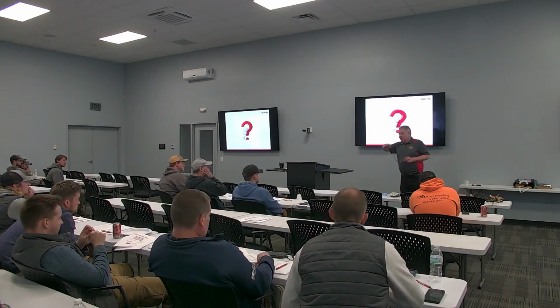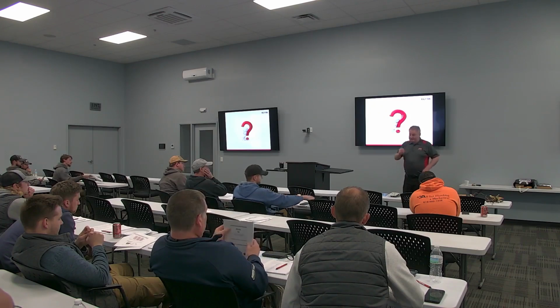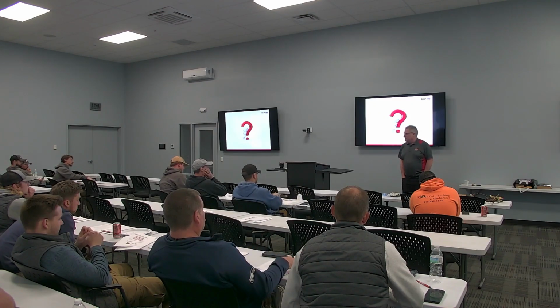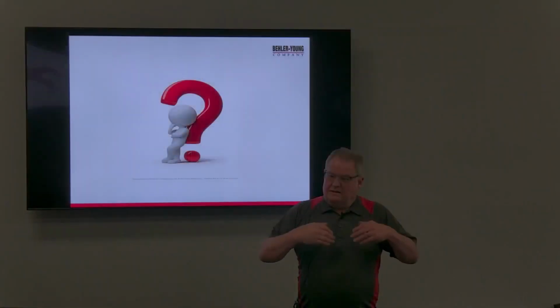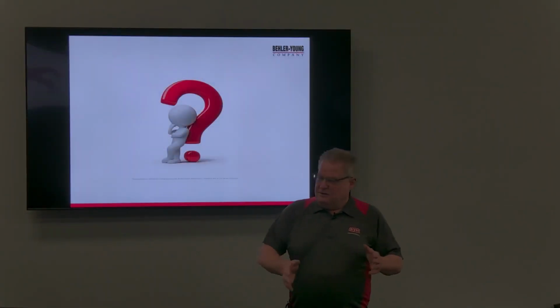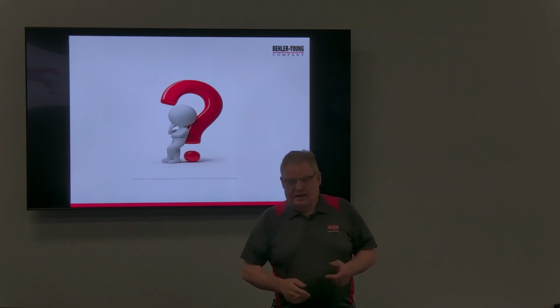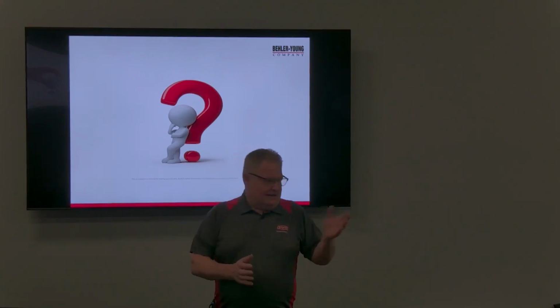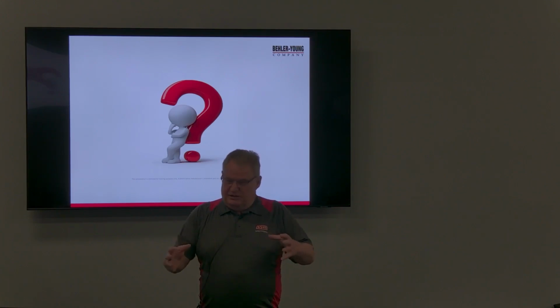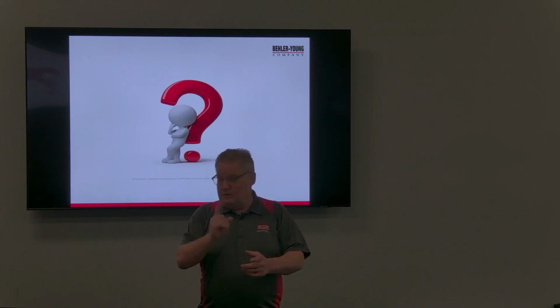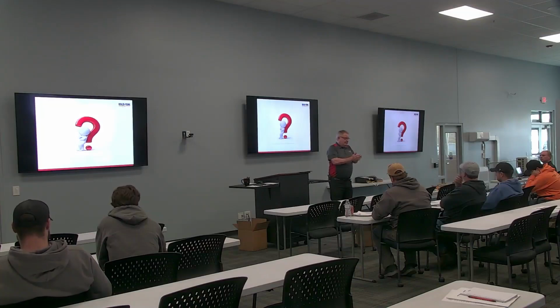So, for those who never lived life without 410, predominantly those of you with no gray hair. When 410 first came out, 410 is a blend. Any refrigerant that begins with a number 4 is a blend, and it is called a zeotrope. Like Dave mentioned a little bit, it's 2 or 3 different refrigerants mixed together to make one new refrigerant. So what happens though is each refrigerant maintains its own boiling point. Maybe this refrigerant boils at minus 40, this one boils at minus 60. So if you have a leak, the one with the lower boiling point is going to boil faster, right?